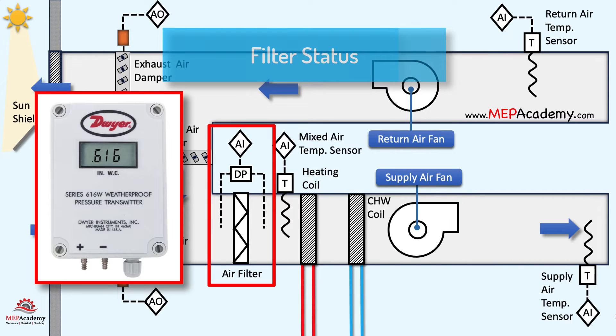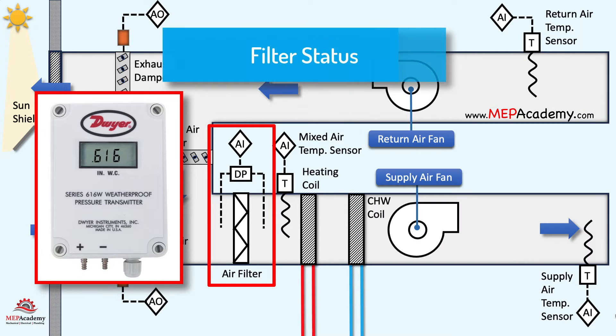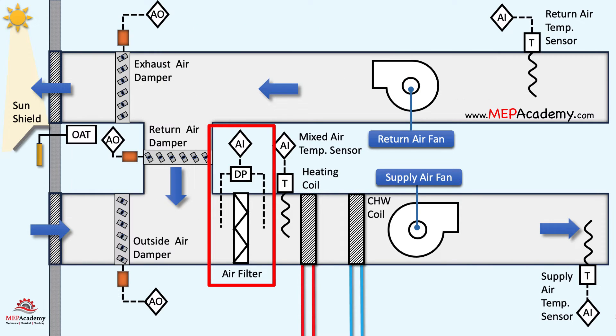The filter differential pressure sensor monitors the pressure drop across air filters. As filters accumulate dust and particulate matter, the pressure drop across them increases. An increase in pressure drop indicates that the air filters are becoming clogged with contaminants. The sensor provides real-time feedback on the differential pressure, serving as an indirect measure of filter cleanliness.